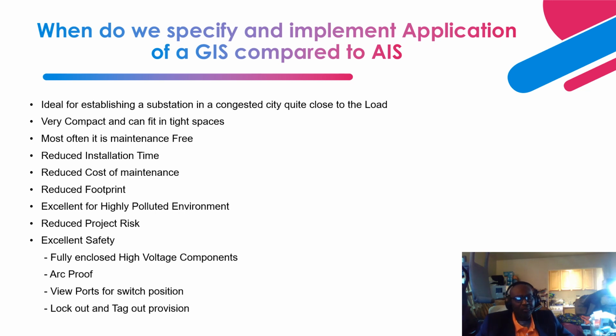And what does it do? Basically, it can result in the flow of a leakage current. The leakage path to ground is reduced and can result in flashover. But you cannot have that in a gas insulated switchgear because everything is in a metal enclosure, compartmentalized, and pressurized with SF6 gas. As such, GIS becomes the best choice and ideal candidate for an environment that is highly polluted.